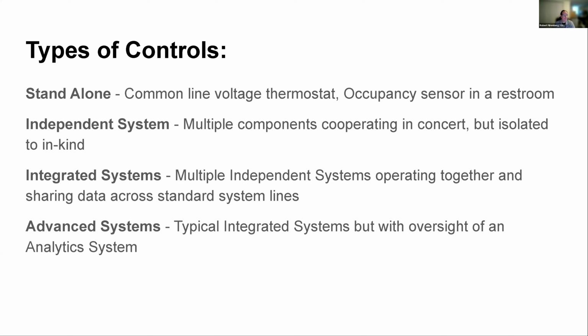Now, what I'm calling advanced systems, these are the new and coming. This is where we start to do a lot more integration between systems. So our lighting system talks to the security system, talks to the HVAC system. So when nobody's in the building, we know that because nobody's carded in, we can have the lights off down to a safety level, and we can have our HVAC in an unoccupied mode.